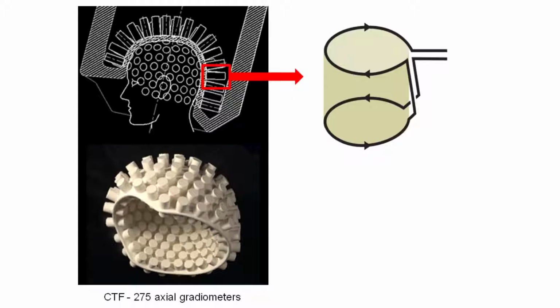In production it is also harder therefore to get them perfectly oriented with respect to each other, compared to the control that you have when you're making chips. Because of this, the cancellation of ambient noise might be less successful. CTF systems therefore use additional reference sensors. As I said before, these are magnetometers and gradiometers located at some more distance from the helmet. These are then used to pick up ambient noise and subtract it from the gradiometers by using a third-order gradient.